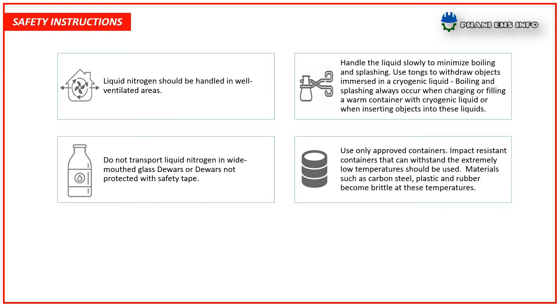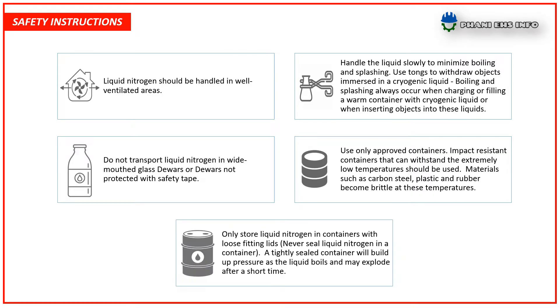Use only approved containers. Impact-resistant containers that can withstand extremely low temperatures should be used. Materials such as carbon steel, plastic, and rubber become brittle at these temperatures.